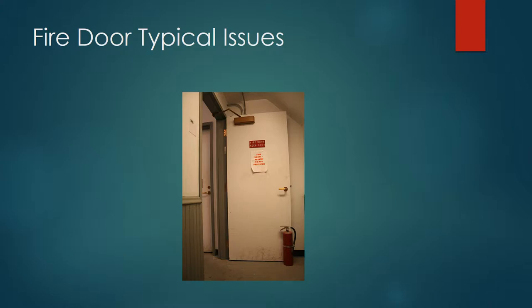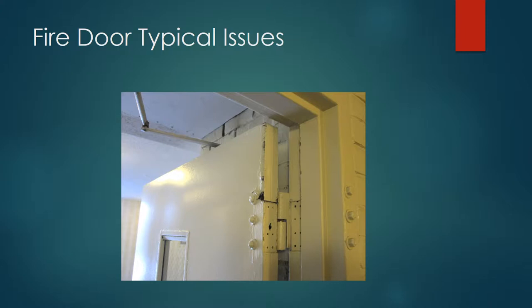Can you find what's going on here? The trained eye might think it's the fire extinguisher not being mounted, or the paper on the door, but really the main issue is the door being propped open. It appears they thought they were providing fire protection for the propped-open door by placing a fire extinguisher there.